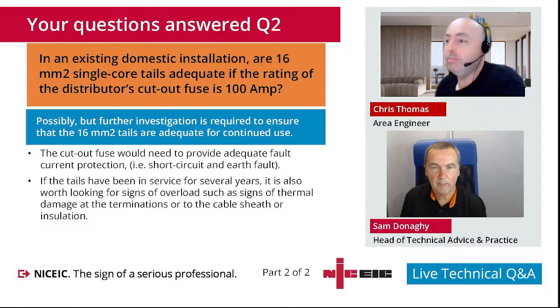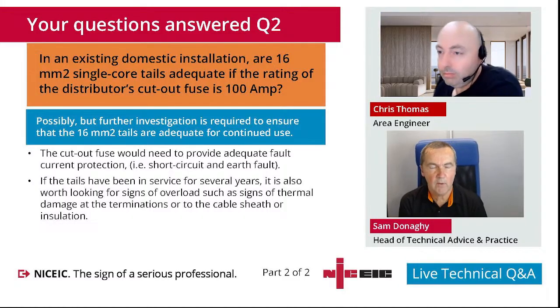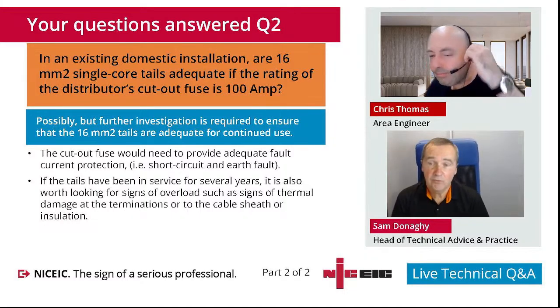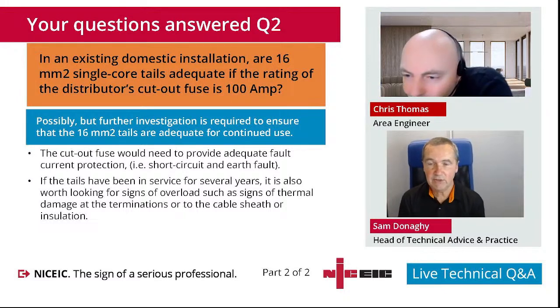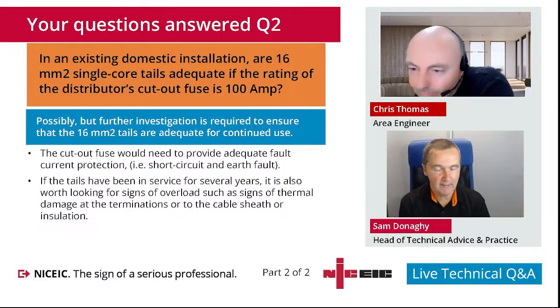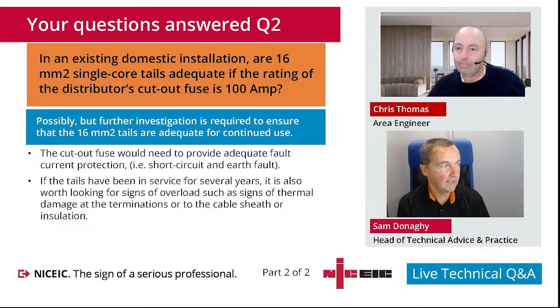Absolutely. I think people look at it, don't they, and they think, well, 16 mil tails won't carry 100 amp, so there must be an issue. Well, only if the installation will draw more than 100 amps. So that's what we need to check. But yeah, people's initial engineering thoughts are right, and that raises the concern then that they should do those additional checks.